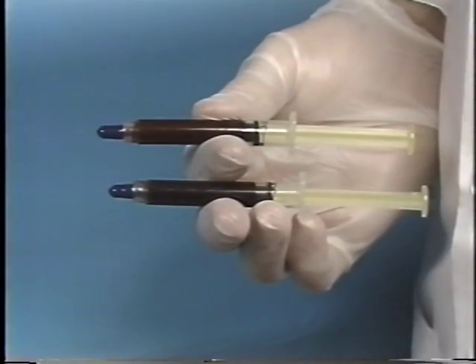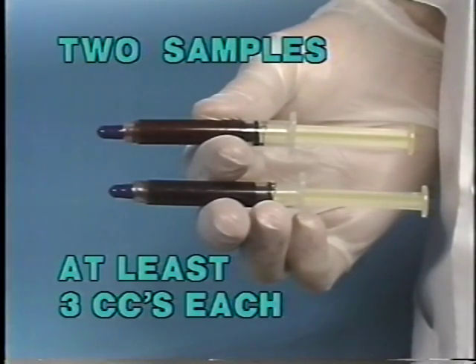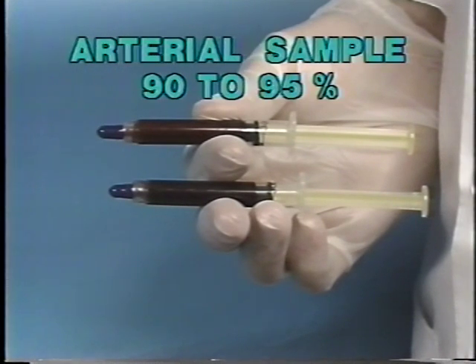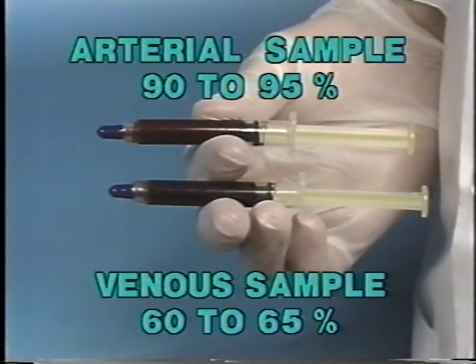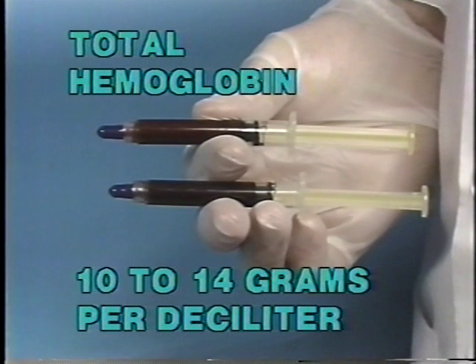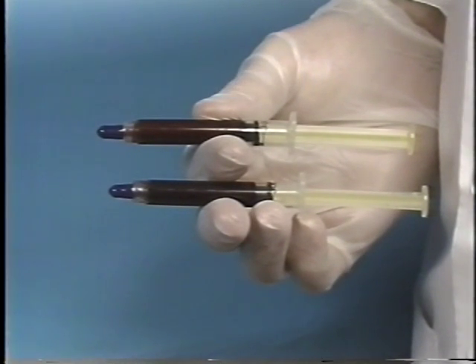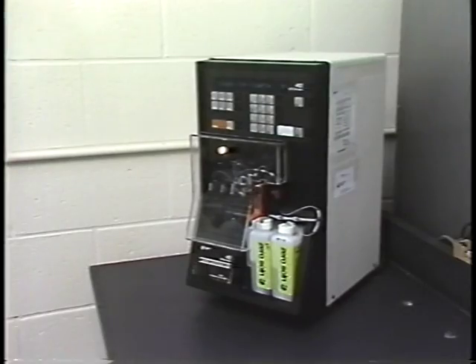Calibration requires the following: 2 blood samples of at least 3 cc's each, an arterial sample of between 90 and 95%, a venous sample of between 60 and 65%, a total hemoglobin of between 10 and 14 grams per deciliter. These samples are to be measured by the hospital's co-oximeter before being used to calibrate the Oxicom 3000.